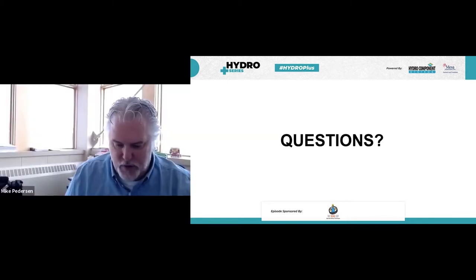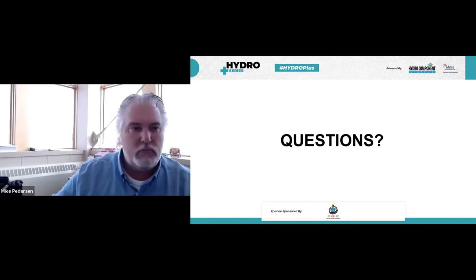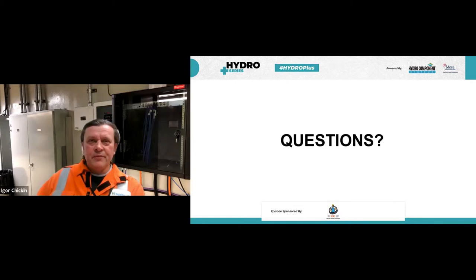One more question here for you, quick, Igor. How do you measure ozone level inside the generator enclosure, and what ozone level is of a concern? Yes, ozone level is a big concern. We measure with portable electronic testing equipment. In our case, we use a 2B Technologies instrument that has a built-in small pump, and a tube goes to the sensor, and we put the sensor in front of the cooler, and that small pump sucks the air, or I mean the gas we are testing, air with ozone in it, and analyzes it and provides us with the readings.